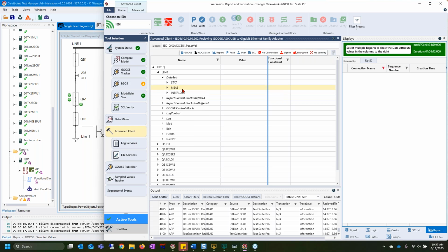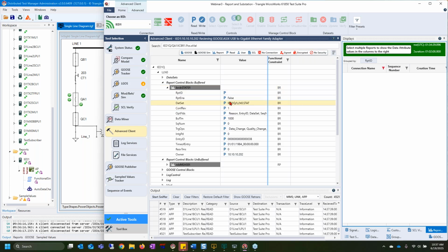So we've got our MMXU, that's our measurement logical node, MX, that's our measurements, and we've got amps and volts all stored within there. Now, a data set doesn't do too much unless you put it inside of a report control block, GOOSE control block, sample values, whatnot. So you'll see right under the data sets here in TSP, we've divided up the report control blocks into buffered and unbuffered. If I open these up, you'll see the buffered report control block, BRCB, and then we've got stat. And sure enough, if you open that up, you'll see the data set being used is stat. We just made the names really convenient, so if you just see the name of a report control block, you know exactly what it is. The B at the beginning stands for buffered, and then the data set name.